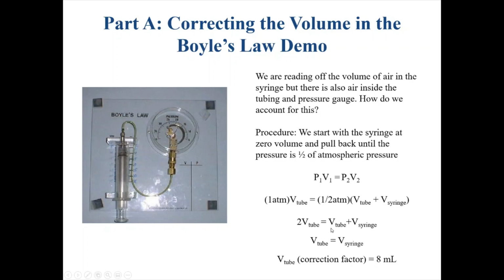Then if we want to get V tube by itself, we can subtract the V tube term from this side and subtract the V tube term from this side. So what we get is, at this condition where we're at 1/2 of the atmospheric pressure, V tube is equal to V syringe. So by pulling it back to 1/2, we know that whatever the syringe value is going to be, that's the volume in that tube. We call this the correction factor. And for today, the correction factor is 8 milliliters. So when we pulled this back, we got 8 milliliters. That tells us that there was 8 milliliters of gas inside the pressure vessel and inside this tubing.